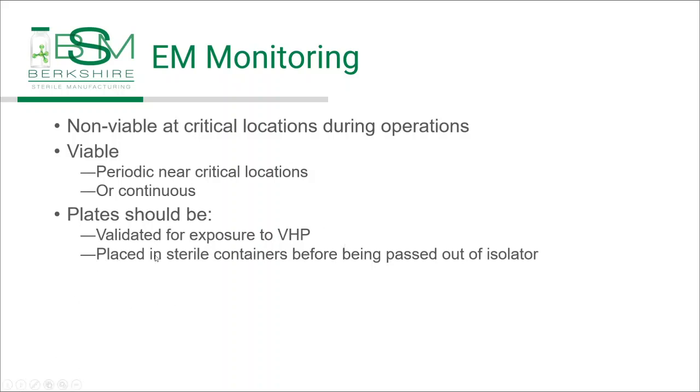Another thing that we found is that plates that are used should be placed in sterile containers before being passed out of the isolator. We did have a period of time where we had a couple of positive hits inside the isolator, which was very surprising. We identified two potential sources of that. One was the handling of the plates.